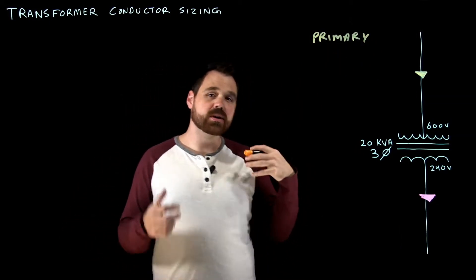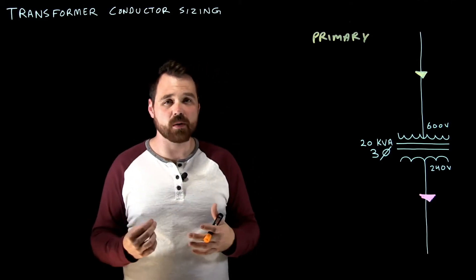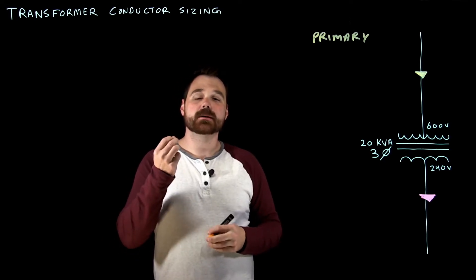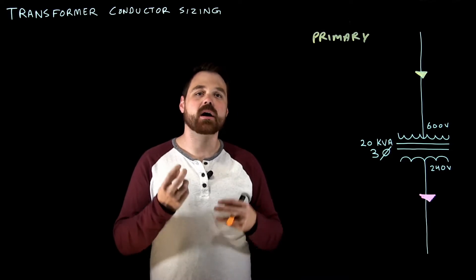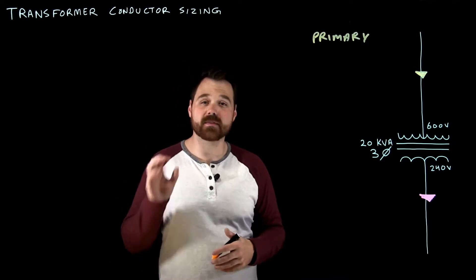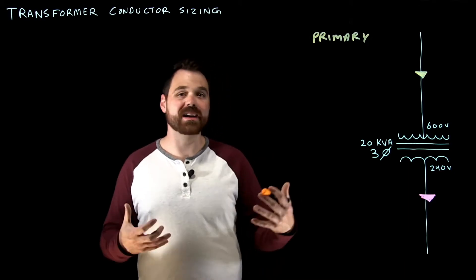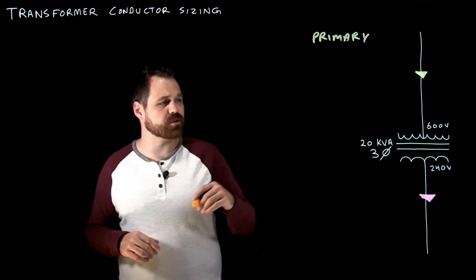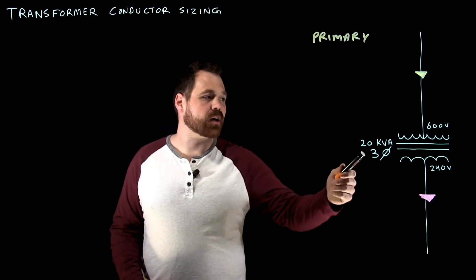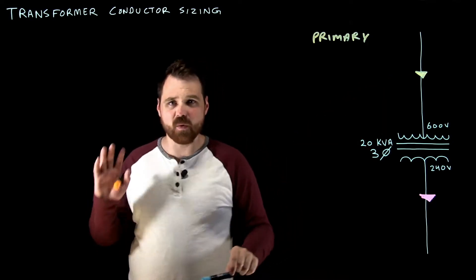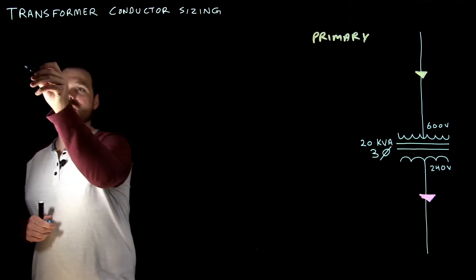So what the code book tells us is the conductor supplying the primary of the transformer needs to be rated for at least 125% of the rated primary current. So the required ampacity of our conductor is 125% the rating of the primary current. So we'll talk about this situation here. I've got a 20 kVA transformer, three phase 600 volts is my primary. Now we're going to calculate that rated current just by taking our formula.